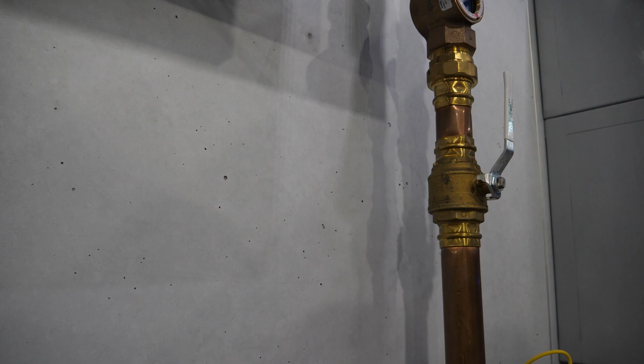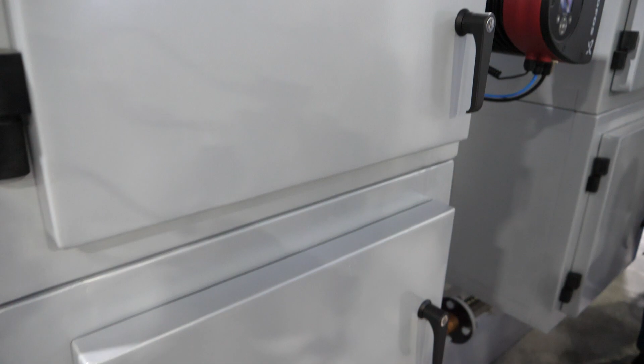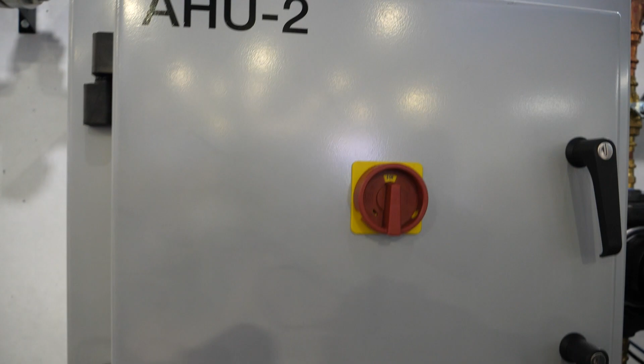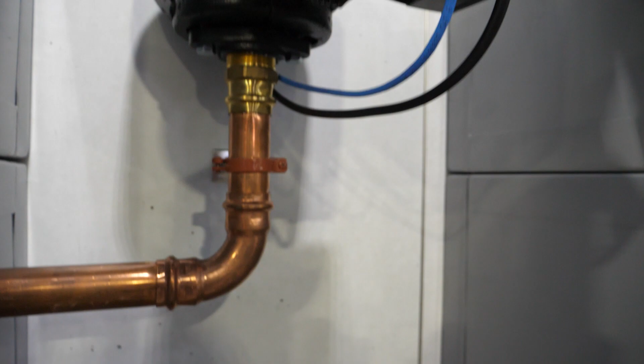What I like about this, Leah, with the decentralized, and I'm a big fan of decentralized, is if you ever had a problem using this system that Grundfos has designed, you're not going to lose the whole building. You might lose a section, and that's something you can easily deal with, whereas if you lose the entire building, doing it some of the, I'm going to call it the other way, it can be a big challenge. A lot of people in the design systems, they don't think about what happens when you have that Saturday night failure.